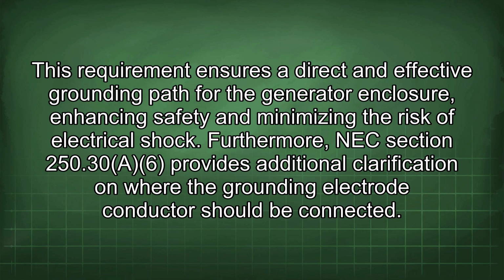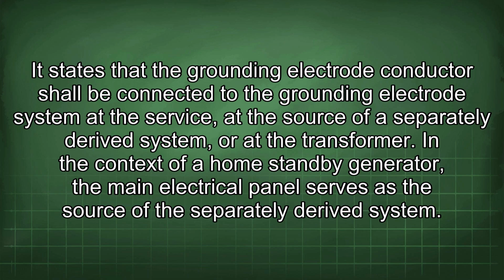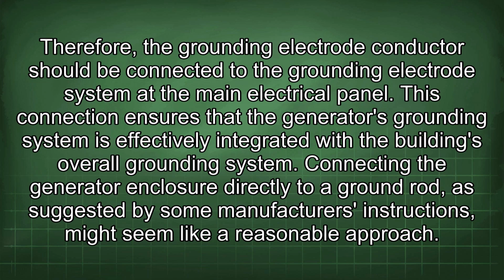electrical shock. Furthermore, NEC section 250.30(A)(6) provides additional clarification on where the grounding electrode conductor should be connected. It states that the grounding electrode conductor shall be connected to the grounding electrode system at the service, at the source of a separately derived system, or at the transformer. In the context of a home standby generator, the main electrical panel serves as the source of the separately derived system. Therefore, the grounding electrode conductor should be connected to the grounding electrode system at the main electrical panel. This connection ensures that the generator's grounding system is effectively integrated with the building's overall grounding system.